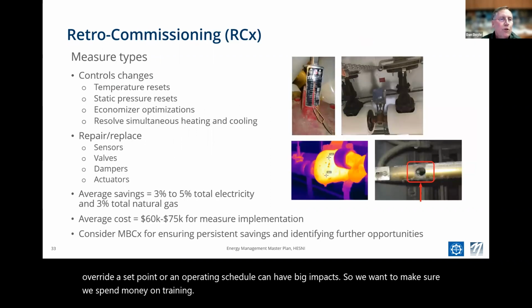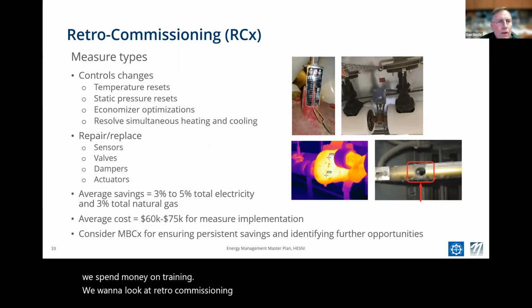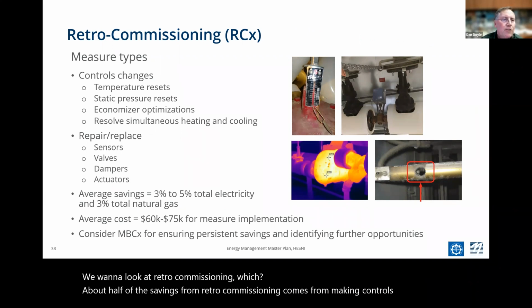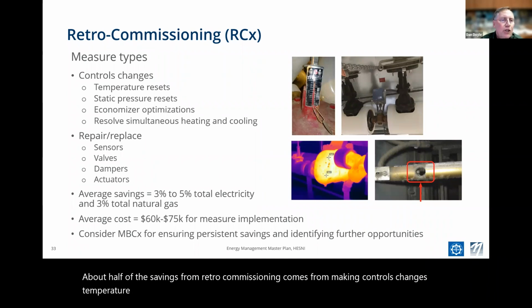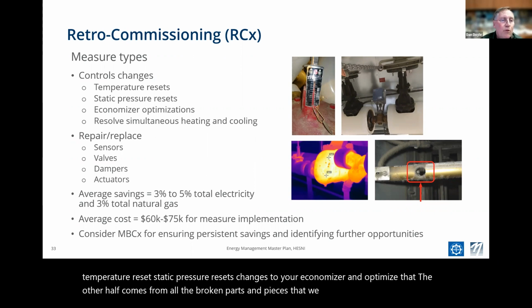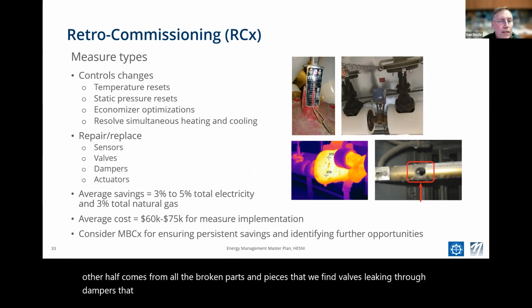We want to look at retro commissioning. About half of the savings from retro commissioning comes from making controls changes—temperature resets, static pressure resets, changes to your economizer to optimize that. The other half comes from all the broken parts and pieces that we find, valves leaking through, dampers that aren't working properly. You can get maybe a 3 to 6% savings by implementing retro commissioning in your facility.